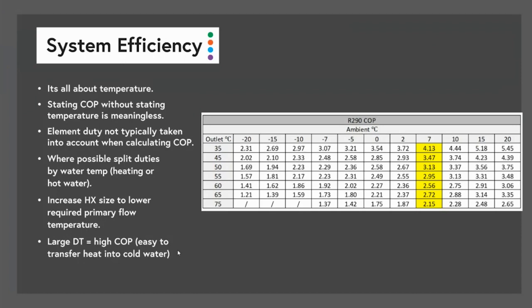So then we could look at, okay, what happens when you take this heat pump and you put it in the middle of central Otago in the winter and you're running radiators, for example. Let's do that. So 10 degrees below, so -10, and then we go up to 65 degrees for radiators. That efficiency is now 1.59, or around 160% efficient. So it's better than electricity, which is 1-to-1 or 100%. So it's certainly still saving you money, but there's a massive difference in the performance of that appliance in different conditions, and that's always going to need to be taken into account.